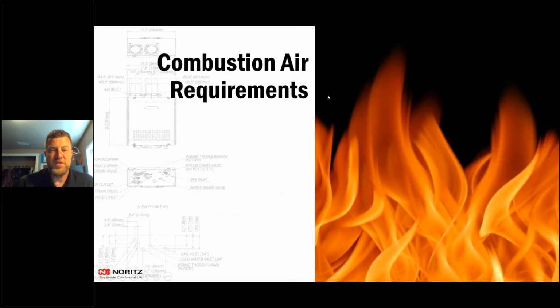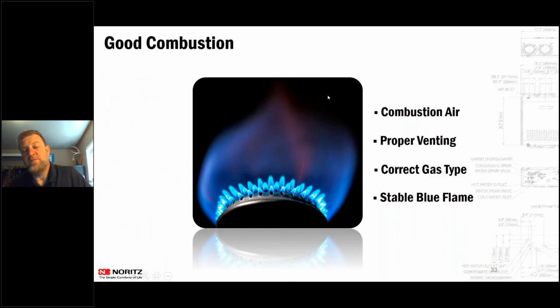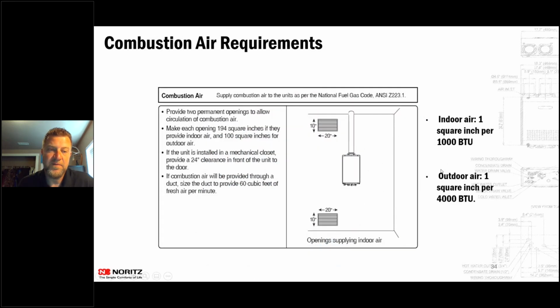Alrighty, we will move on to combustion air. Every gas-burning appliance needs combustion air to operate. In this section we'll cover combustion air, proper venting, correct gas type, and what the flame should look like. Any flame with natural gas or propane should be a nice blue flame. If you're getting a yellow flame, you just don't have the right air to gas mixture. With tankless water heaters, you can pull combustion air from either inside the house or from outside the house.